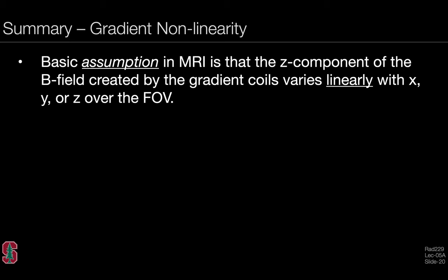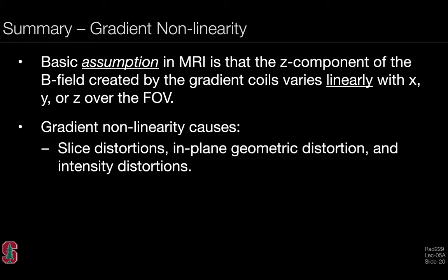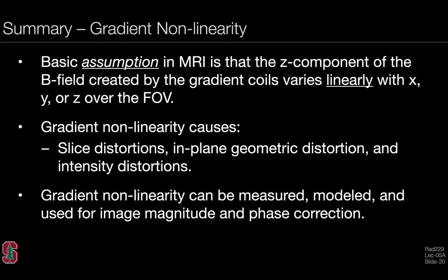In summary, let's remember that there's a basic assumption in MR that the z component of the B field created by the gradient coils varies linearly with x, y, or z over the field of view. In fact, we know our gradients to be nonlinear, and gradient nonlinearity causes several problems including slice distortions, in-plane geometric distortion, and intensity distortions. Gradient nonlinearity can be measured, modeled, and used for image magnitude and phase correction. We didn't spend a lot of time talking about phase corrections, but any time the magnitude of our signal is corrupted, the phase is corrupted as well.